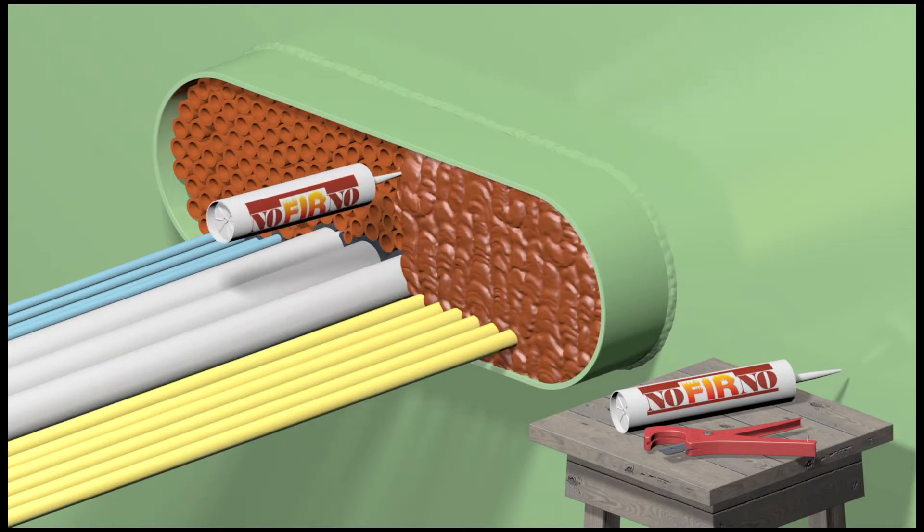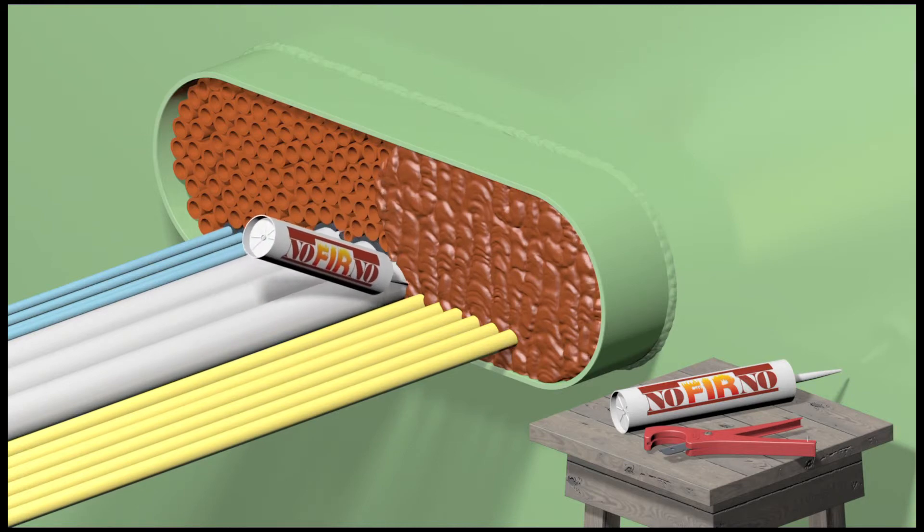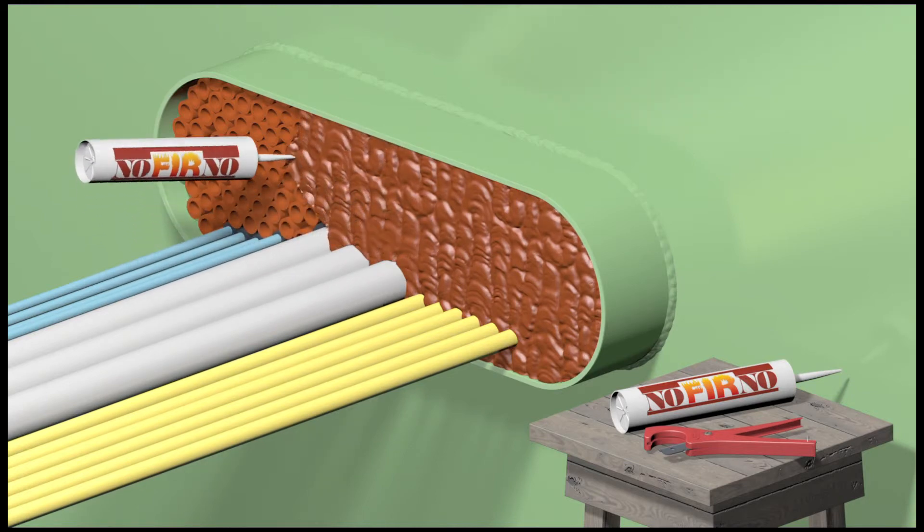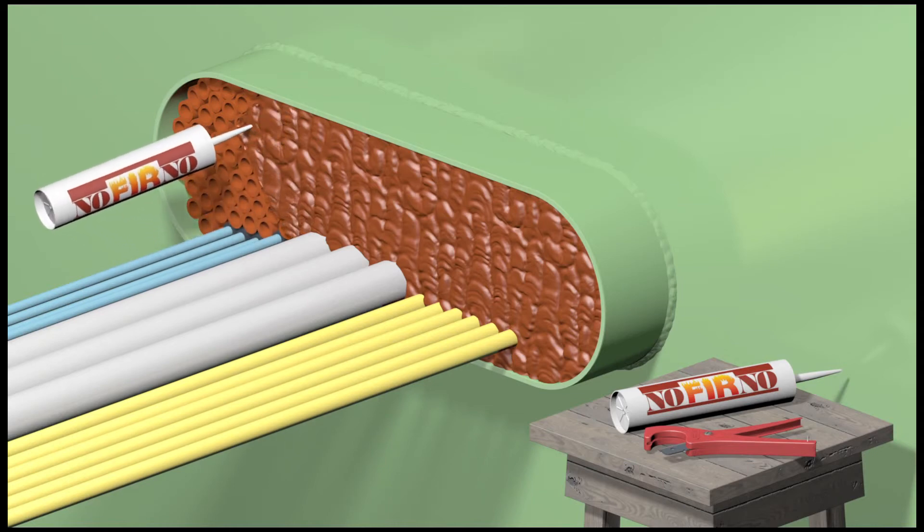A 20 millimeter layer of Nofirno sealant is applied at each side of the Nofirno multi-cable transit. Skin formation of the sealant takes place after 10 to 15 minutes.